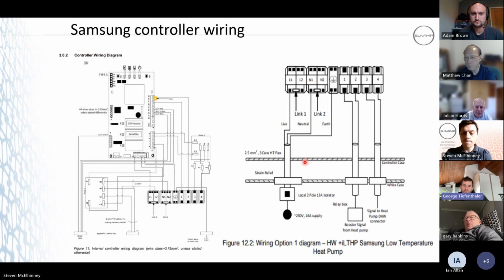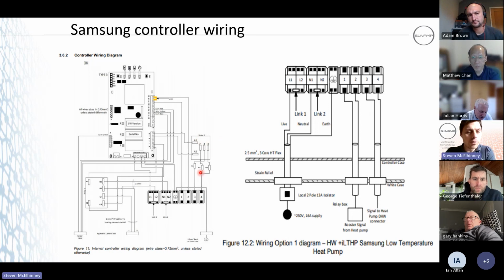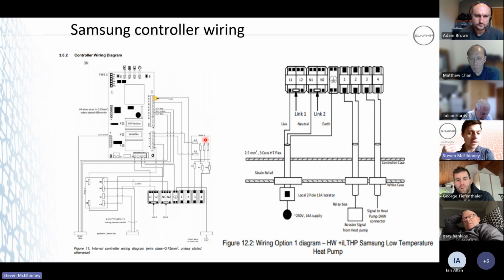So that's reading a resistance then, T3, T4. Basically, yeah. Can you not do that with a boiler? This is in the Samsung controller, is it? Yeah, this is a Samsung. What we've got here is 3 resistors. When the heat battery is up to temperature, it'll be sending a fixed value resistance to their controller, which is going to be about 77 degrees. When there's a demand, that fixed value then changes to 40.